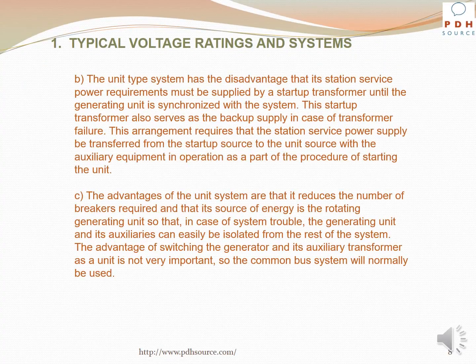The unit type system has the disadvantage that its station service power requirements must be supplied by a startup transformer until the generating unit is synchronized with the system. This startup transformer also serves as the backup supply in case of transformer failure. This arrangement requires that the station service power supply be transferred from the startup source to the unit source with the auxiliary equipment in operation as a part of the procedure of starting the unit.